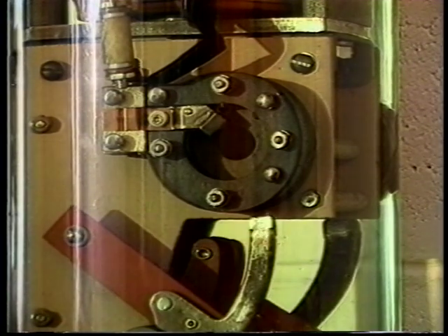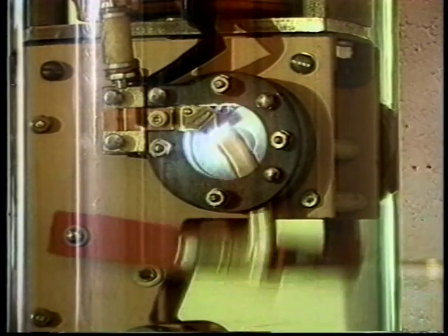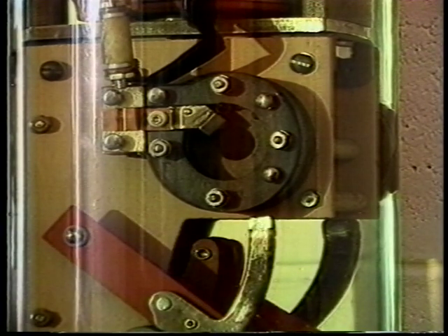Interrupter. The interrupter is the part of the recloser that contains separable contacts which operate within an interrupting unit. The physical configuration and method of interruption varies with manufacturer and recloser classification.